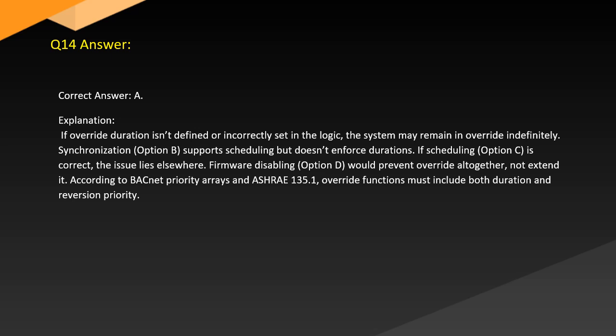Answer. Correct answer: A. Explanation. If override duration isn't defined or is incorrectly set in the logic, the system may remain in override indefinitely. Synchronization, option B, supports scheduling but doesn't enforce durations. If scheduling, option C, is correct, the issue lies elsewhere. Firmware disabling, option D, would prevent override altogether, not extend it, according to BACnet priority arrays and ASHRAE 135. Key point: override functions must include both duration and reversion priority.